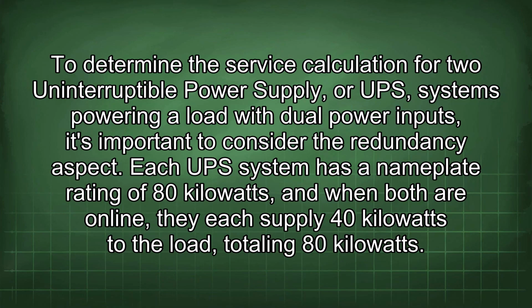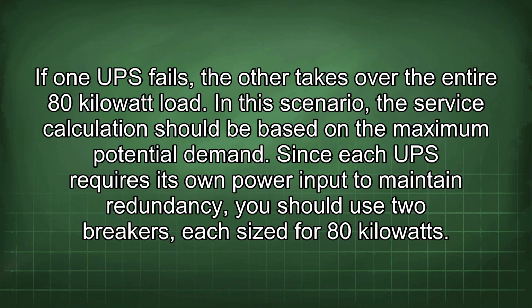To determine the service calculation for two uninterruptible power supply (UPS) systems powering a load with dual power inputs, it's important to consider the redundancy aspect. Each UPS system has a nameplate rating of 80 kilowatts, and when both are online, they each supply 40 kilowatts to the load, totaling 80 kilowatts. If one UPS fails, the other takes over the entire 80 kilowatt load. In this scenario, the service calculation should be based on the maximum potential demand.